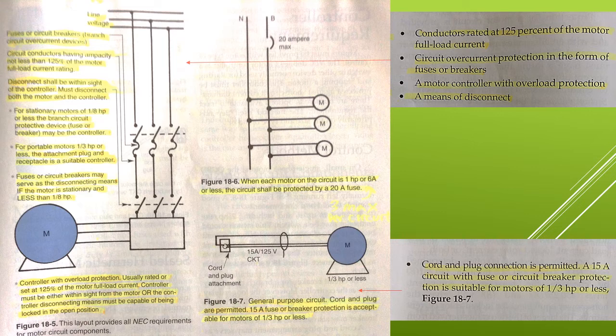Motor branch circuit. Each motor needs motor running overcurrent protection. This protection must not exceed the amperage stamped on the OCPD of the smallest motor on the branch circuit. The OCPD must be approved for group installation in multiple motor circuits. Each motor may have an individual disconnect, but it is not necessary. A single disconnect for a group of motors is permitted if all of the motors are parts of one machine.